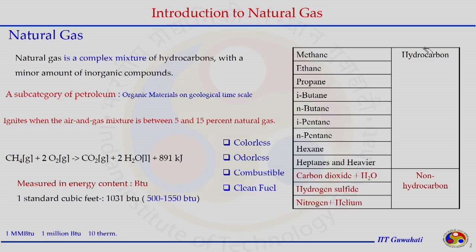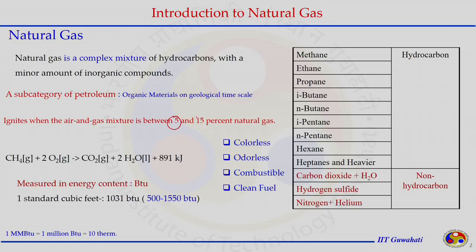Natural gas ignites when the air-gas mixture is between 5% and 15%. The 5% is the lower explosive limit and 15% is the higher explosive limit. The combustion reaction is: CH4 + 2O2 gives 1 mole of CO2 and 2 moles of H2O, with energy generation of 891 kJ/mol.